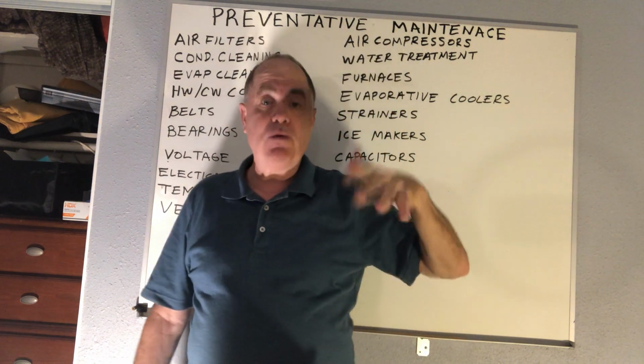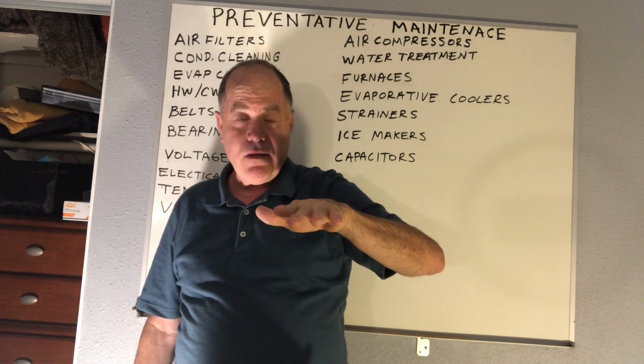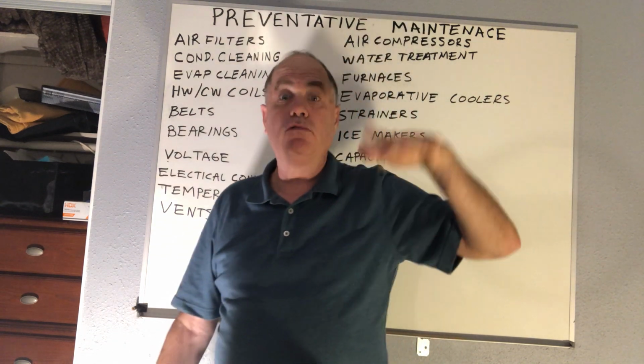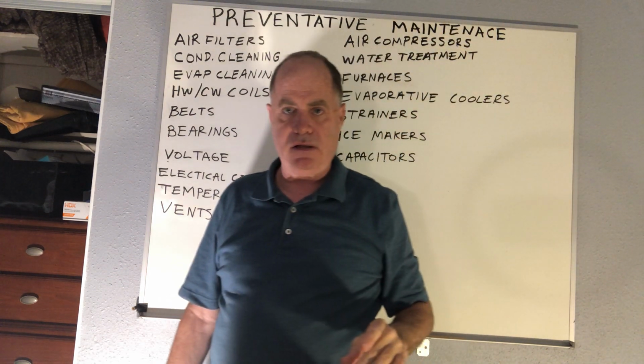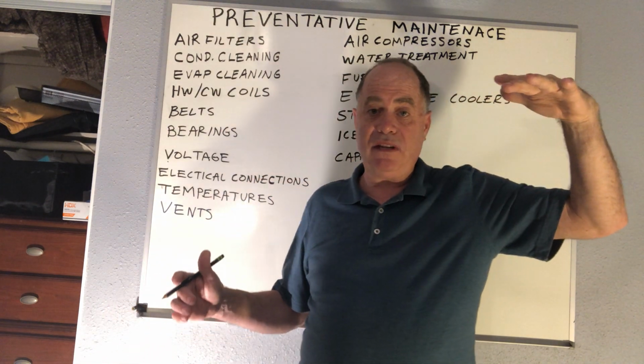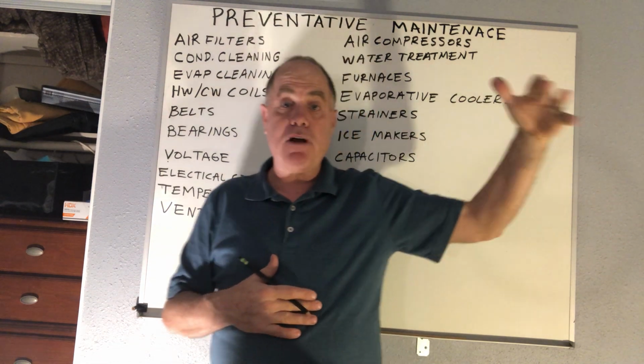You know, and by the way, it's a little counterintuitive. If you have a plugged air filter that's restricting the airflow and just letting a little bit of air through, not much at all, it'll raise it 65 or 70 degrees. Because it slows down the air, it has longer to come in contact with the heat exchanger, but you're not getting enough air out of your vent. And it may be tripping off on high limit.